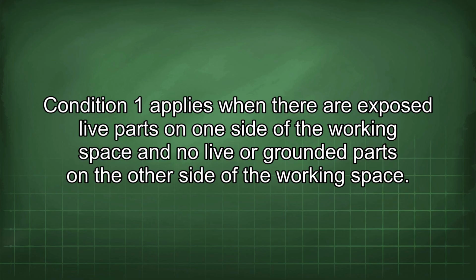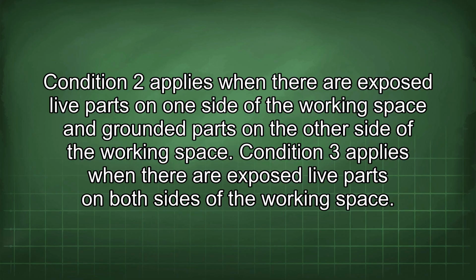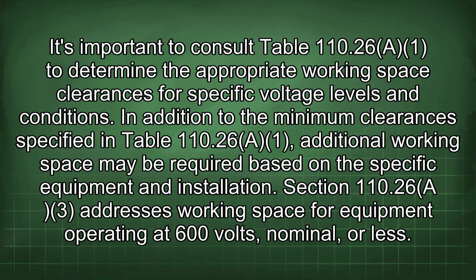Condition 1 applies when there are exposed live parts on one side of the working space and no live or grounded parts on the other side of the working space. Condition 2 applies when there are exposed live parts on one side of the working space and grounded parts on the other side of the working space. Condition 3 applies when there are exposed live parts on both sides of the working space. It's important to consult Table 110.26(A)(1) to determine the appropriate working space clearances for specific voltage levels and conditions.